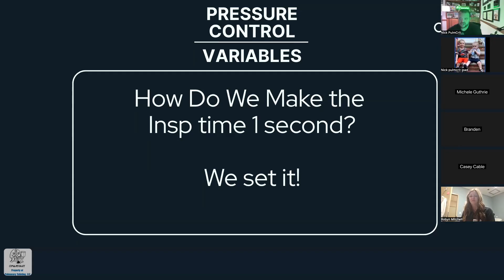So 1 second, 0.8 seconds, 0.9 seconds, whatever it is. You set the I time. When you set up PRVC tomorrow or tonight, if you're working, look at what you set. You set an I time. You set a volume, but you also set an inspiratory time. One of the reasons that PRVC is a pressure controlled mode. So then, in pressure control, can we set the flow?